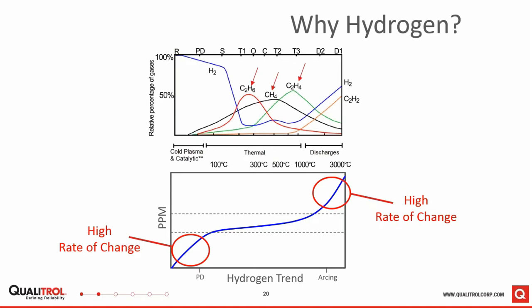Okay, so the increase in hydrogen is due to something getting very hot inside the transformer, breaking down the oil, which is a hydrocarbon molecule, and that releases free hydrogen and carbon that many times ends up turning into carbon monoxide, carbon dioxide, or your methane, ethane, or ethylene.